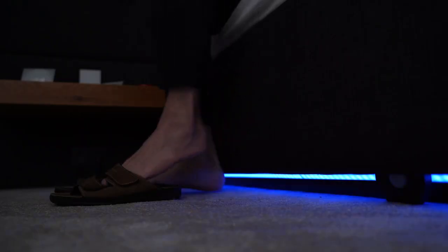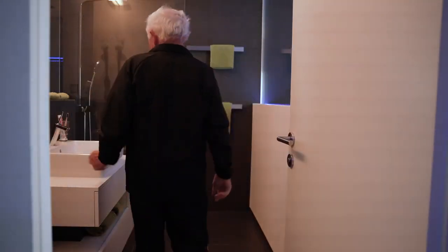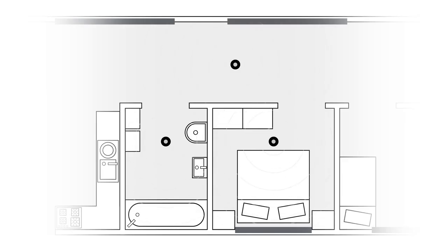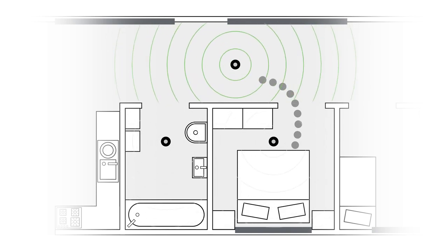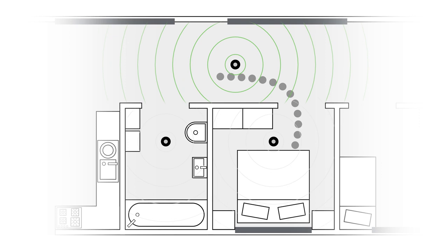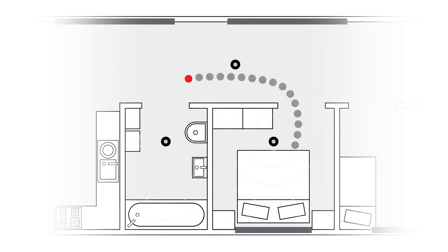The fall control triggers an alarm chain as soon as there is a fall from which you cannot recover on your own. The principle behind it works like this. If a resident gets out of bed at night to go to the toilet, for example, the presence detector in the bedroom detects the movement and a follow-up time begins in which further movement must be detected before the alarm starts. If the person now walks down the hall towards the bathroom, the next presence is detected here and a new run-on time begins. If the person falls down and stops moving within the range of the presence detector in the bathroom, an alarm is triggered after the defined run-on time.